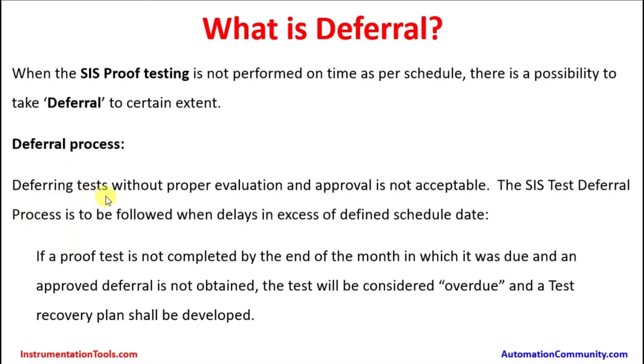Deferral process: deferring a test without proper evaluation and approval is not acceptable. The SIS test deferral process is to be followed when delays are in excess of the defined schedule date. If a proof test is not completed by the end of the month in which it was due and an approved deferral is not obtained, the test will be considered overdue and a test recovery plan shall be developed. Normally one month is allowed, with the end of the calendar month as the deadline.